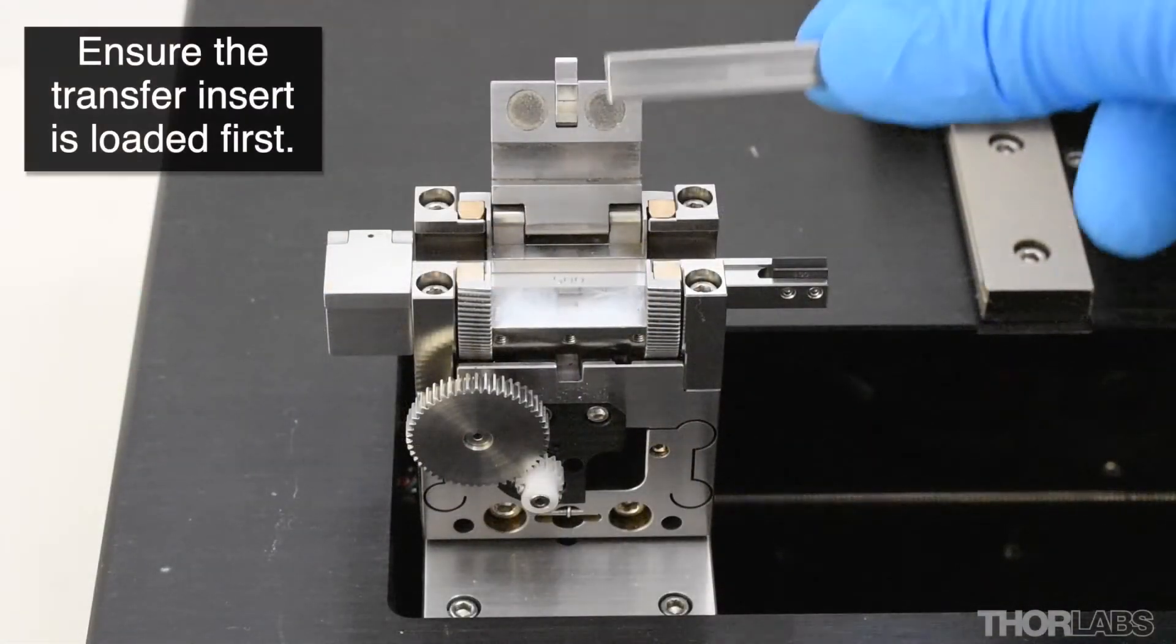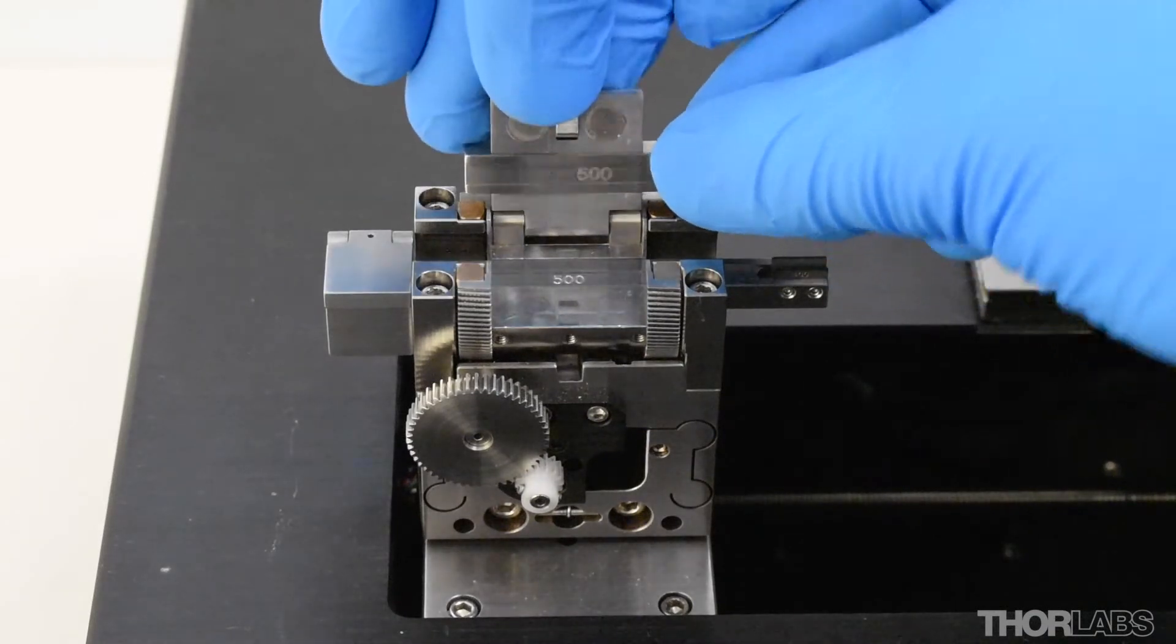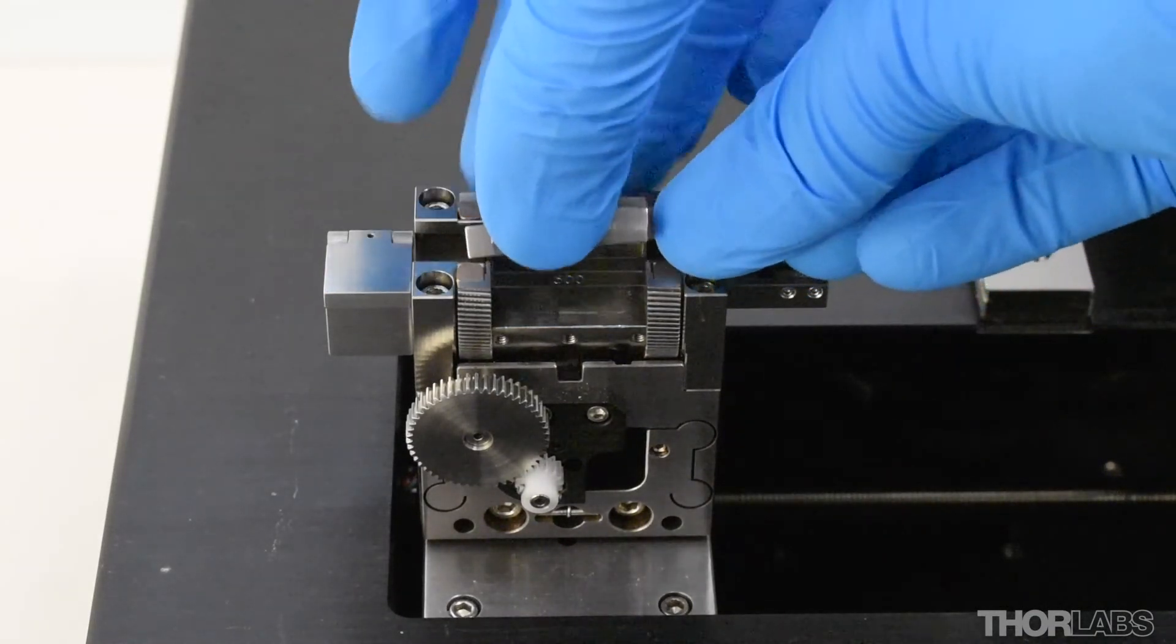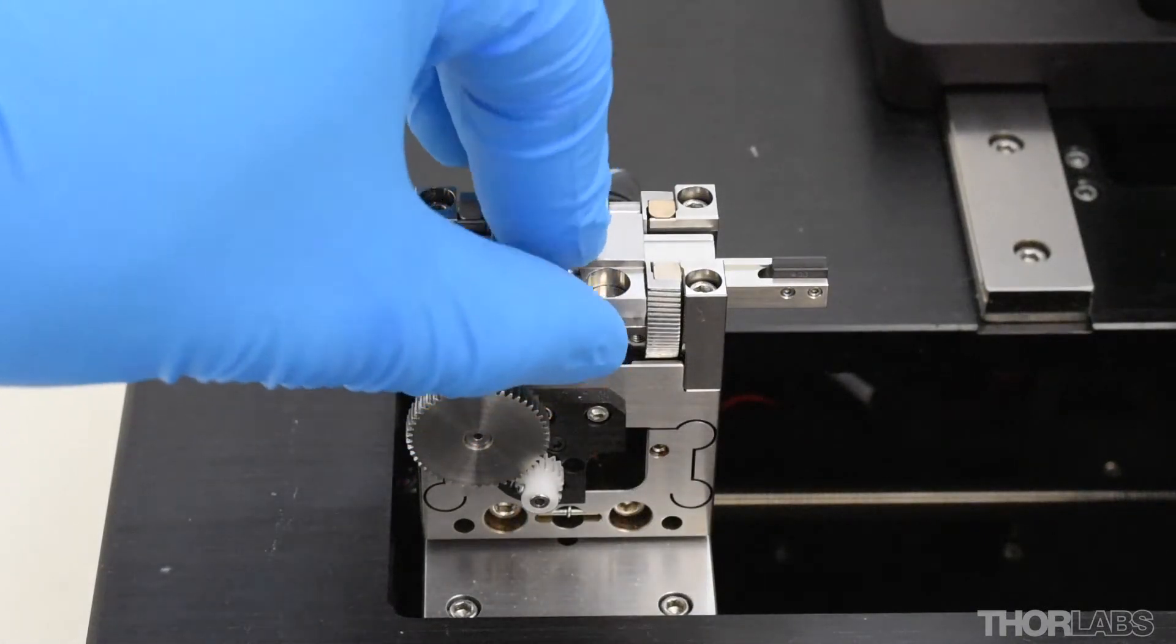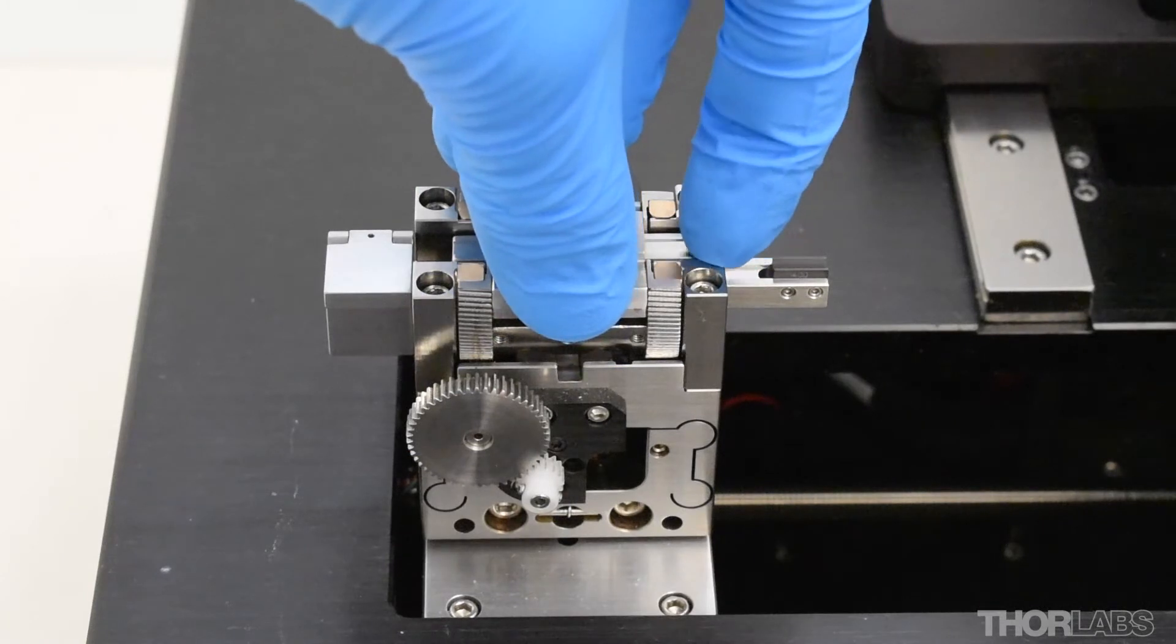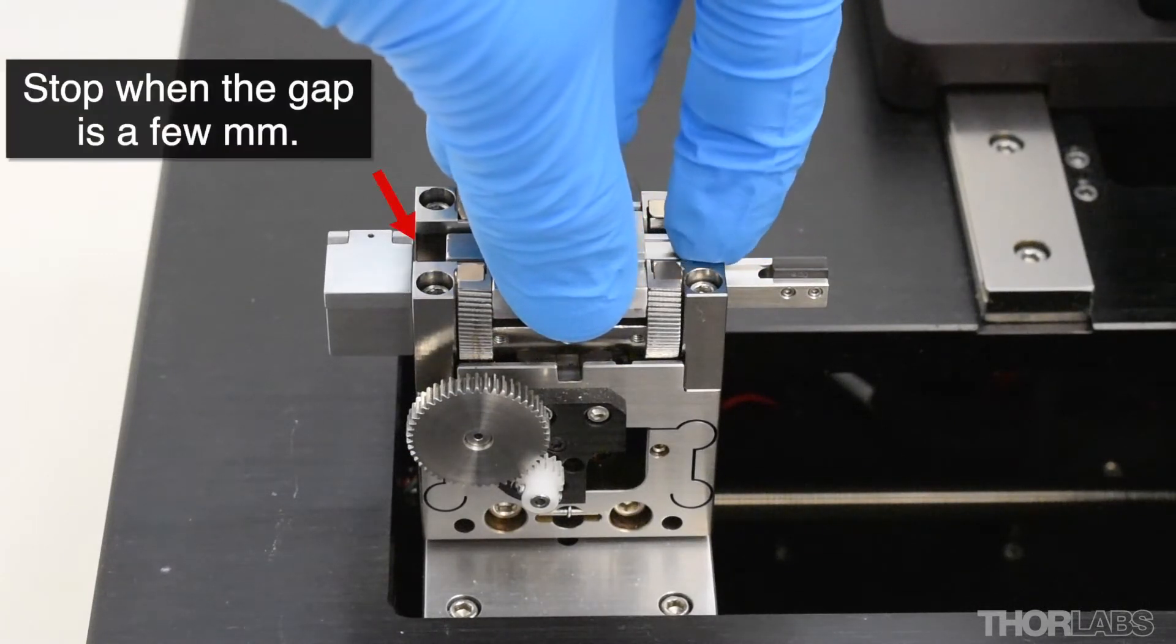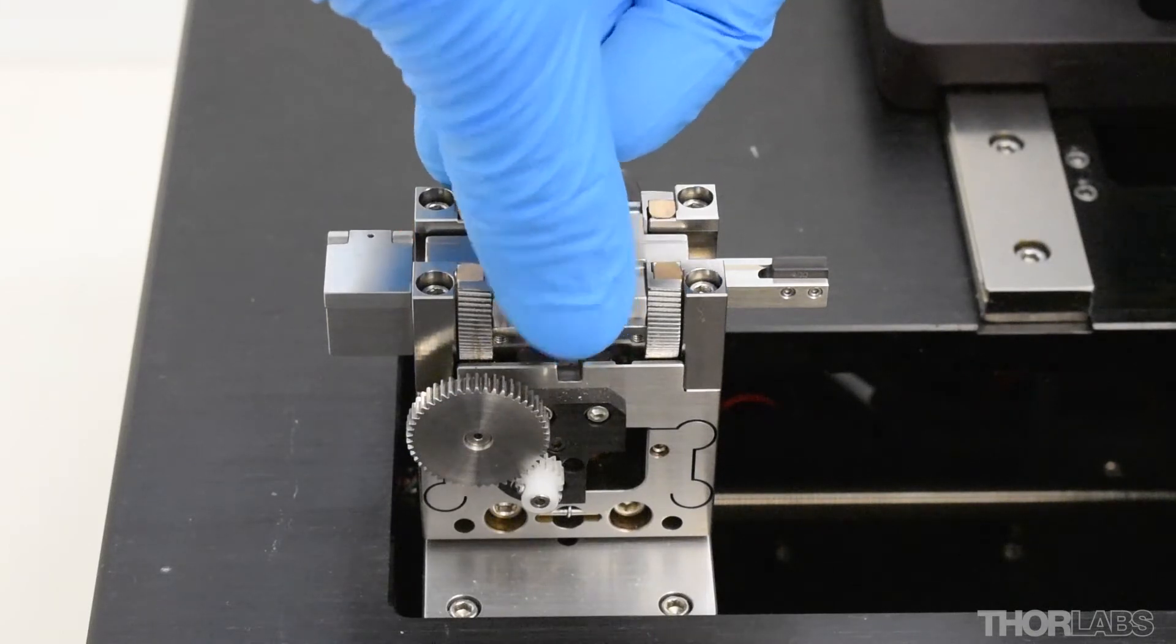Using the same method as described earlier, place the upper insert into the lid of the fiber holding block. Close the lid while holding onto the insert so that it stays in place. Now slightly lift the lid and slide the upper insert towards the transfer clamp. Stop when there is a gap of a few millimeters between them. Allow the lid to close fully.